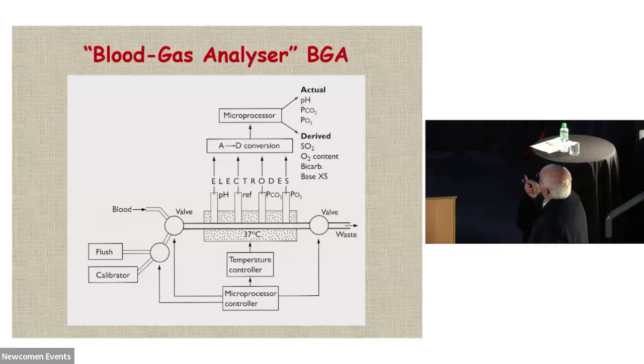And the tube passes through a device which keeps it at 37 degrees, in other words, the temperature it was in the human body. And it passes through a pH electrode, a reference electrode, PCO2 electrode, and a Clark oxygen electrode. They're all very, very small, so it'll still work off that amount of blood. And an A to D conversion microprocessor will give you those important values there, partial pressure of CO2 and oxygen, and also measure the pH, which is very important.